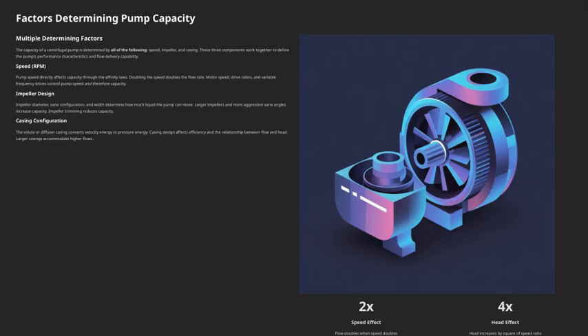Now, to understand how these factors interact, let's look at some key effects related to speed. When speed doubles, the flow doubles as well. However, the height the pump can lift actually increases by the square of the speed ratio. Power consumption, on the other hand, increases by the cube of the speed ratio. So a small increase in speed can lead to a much larger increase in power demand. By understanding these interactions, we can better predict how a pump will perform, troubleshoot capacity issues, and select the right pump for specific applications. Manufacturers provide performance curves that show how capacity varies with both impeller size and speed for each casing size, helping us make informed decisions.